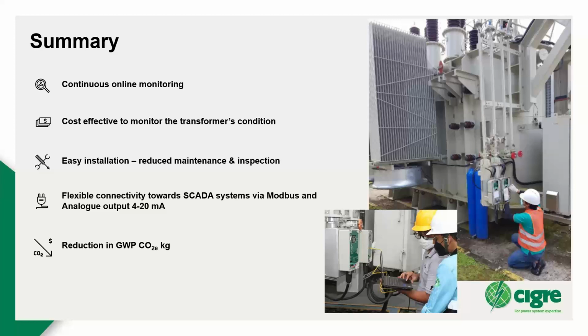Now in the market, there are many new state-of-the-art breathers that give you the possibility to connect these devices to your SCADA system via Modbus, analog outputs, and other means, giving you a good understanding of your entire fleet and what's happening with your transformers. Finally, adopting this technology reduces the actual amount of silica gel used in transformers, leading to a significant reduction in the global warming potential factor associated with self-dehydrating breathers. So that's all from my side.